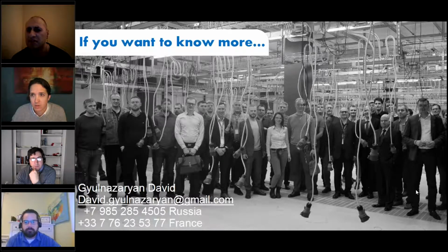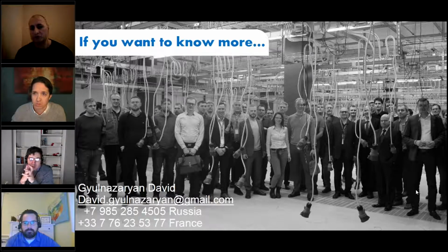Sorry, could you repeat, please? The purpose, what are we seeking to do in this discussion today? What's the next step that you want from this program? The next step is to create the same rules without bottlenecks for air cooling of OCP modular data center. The aim is to implement rules which let the OCP modular data center work without overpressure, without hotspots, and with the possibility to work with air-cooled chillers, but up to 30-40 kilowatts per rack. This is the driver for why people move from air-cooled servers to immersion cooling or high-performance cooling.